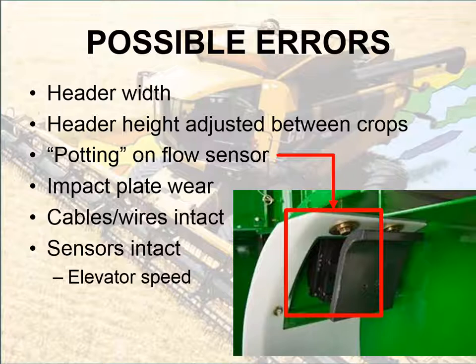Along with that, make sure your sensors are intact and working, things like your elevator speed or header height sensor. These are where most of the errors occur, in the examples I presented here. That's always the first place to start. If things aren't working, check your cables, check your wires, check the potting on your flow sensor.